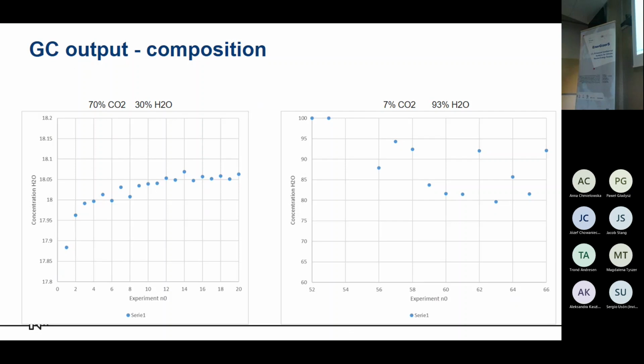And here is the output from the GC, and for the mixture of 70% of CO2, we have very stable results. So for this mixture, everything is okay. The settings of the GC are very well adjusted, but for the 7% of CO2, the results are very different, from 95% of water to 80%. So it means that we potentially have condensation in the system, or the GC is not calibrated very well for this mixture. So it is important to have stable results.